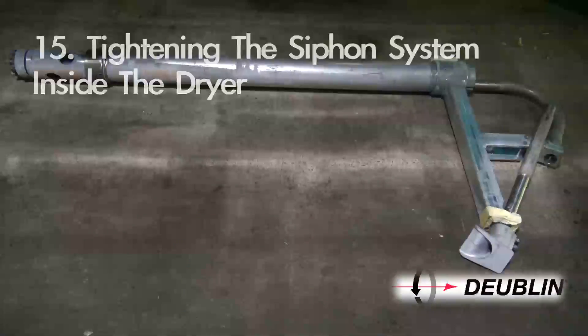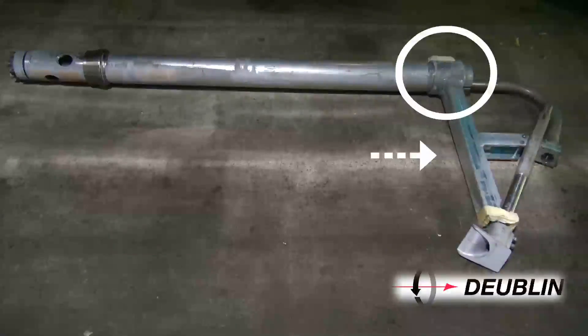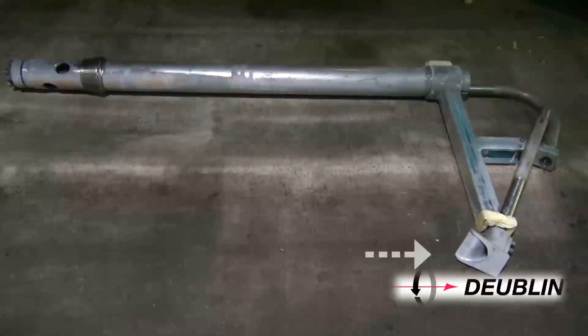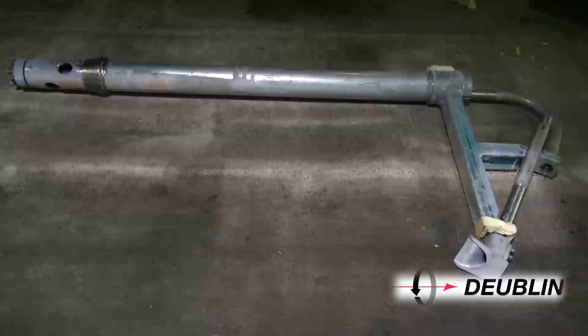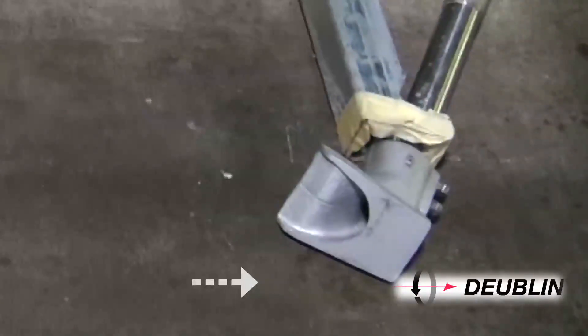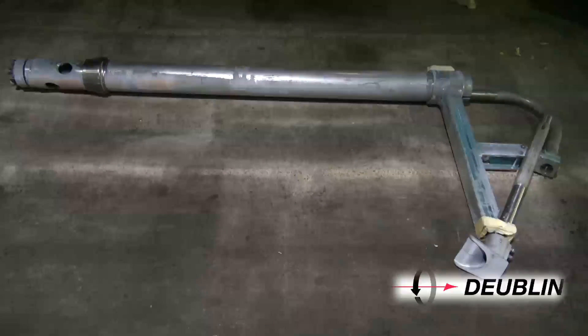Step 15: Tightening the siphon system inside the dryer. Adjust the axial position of the vertical support by sliding it along the horizontal support so that the siphon shoe is in the proper position. Check the location of all counterweights for interference with the stationary siphon and relocate where necessary. Place the appropriate gauge to set the height of the back of the siphon shoe for clearance as recommended by Deublin. Tighten all connections.